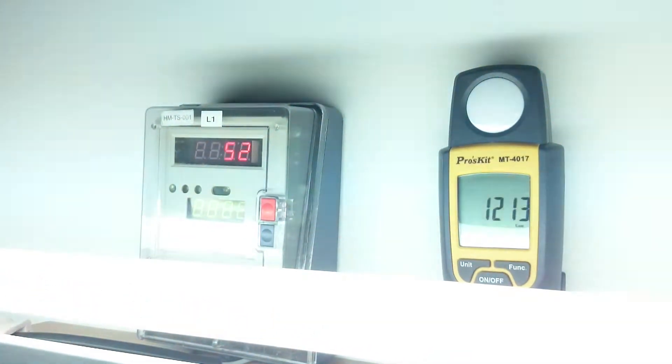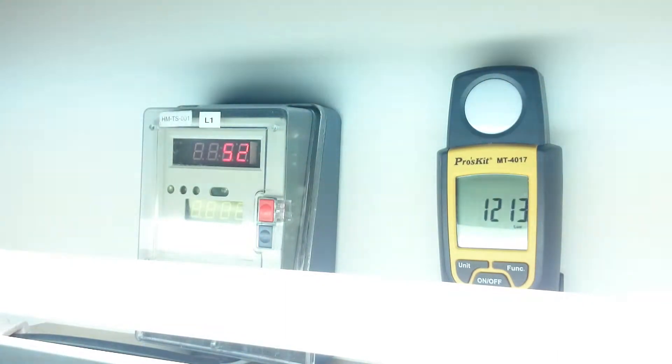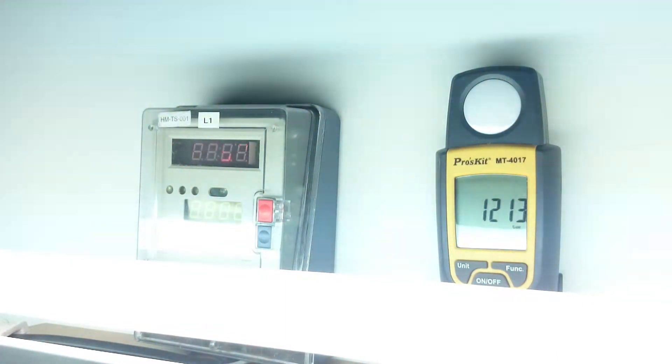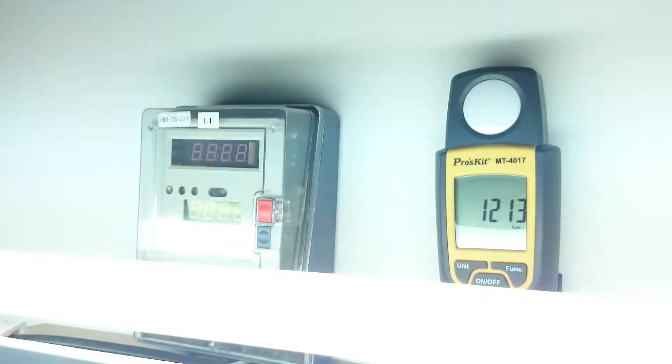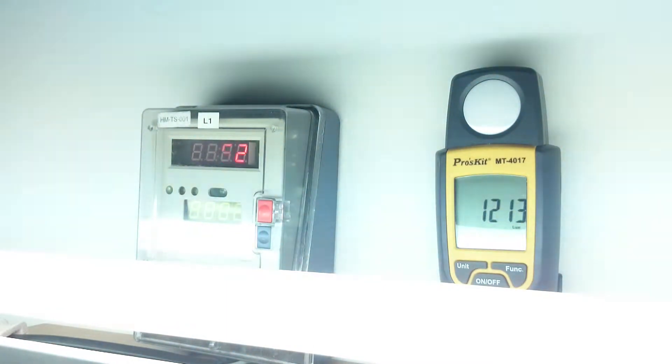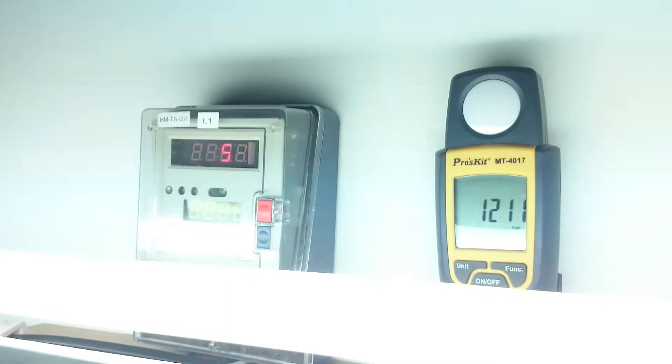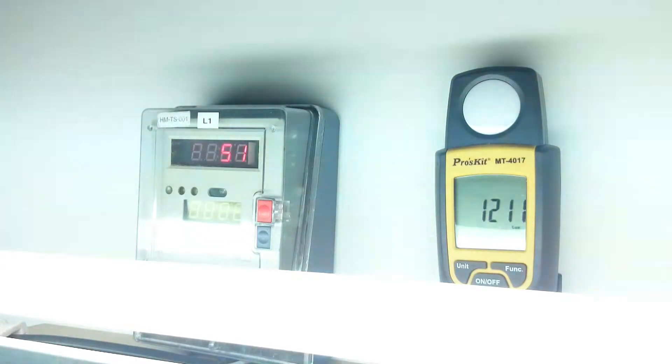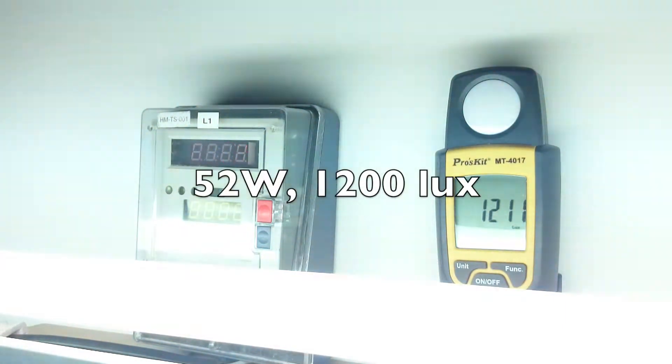As you can see at 100% power it's at 52 watts. That is 36 watts for the fluorescent light itself. Then there is an additional 10 or 11 watts of power consumption for the magnetic ballast. And then the C-Light segment controller has a self power consumption of about 5 watts. So at 100% power you can see the brightness on the right side at about 1200 lux.